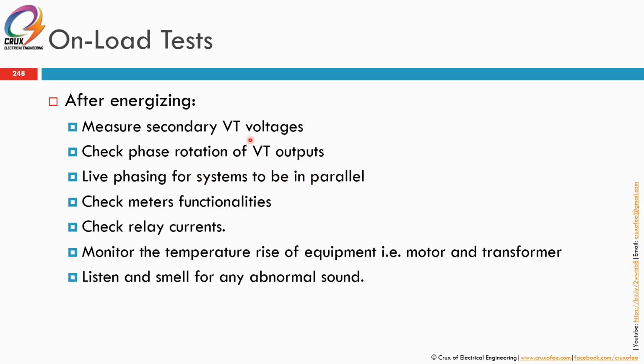So for 33 and 132 kV, you must make sure that the secondary circuit of the VT are all correct. If not, it will give you the wrong reading and you might close and parallel your high voltage system to a phase-to-phase fault, okay, because of the wrong connection of the secondary VTs. You also check the meter's functionalities. Maybe there was some error in terms of the ratio set within the relay, and check the relay currents and monitor the temperature rise of the equipment.